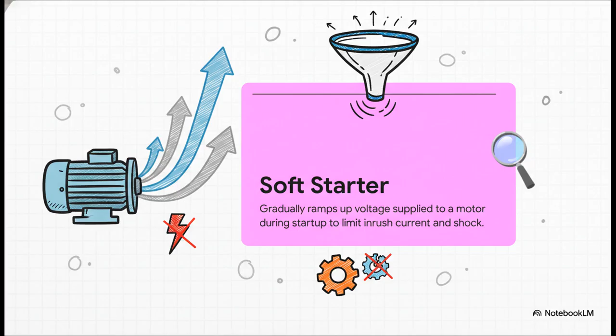The thing you have to remember is this. Once that motor is at full speed, the soft starter's job is totally done. So it all happens in a simple 3-step process. First, it limits that initial voltage hit. Second, it slowly ramps that voltage up until the motor hits its full, single speed. And then third, and this is really the key, it bypasses itself. An internal switch closes, and the motor just runs directly off the main power. The soft starter is basically just sitting there, inactive, while the motor does its thing.